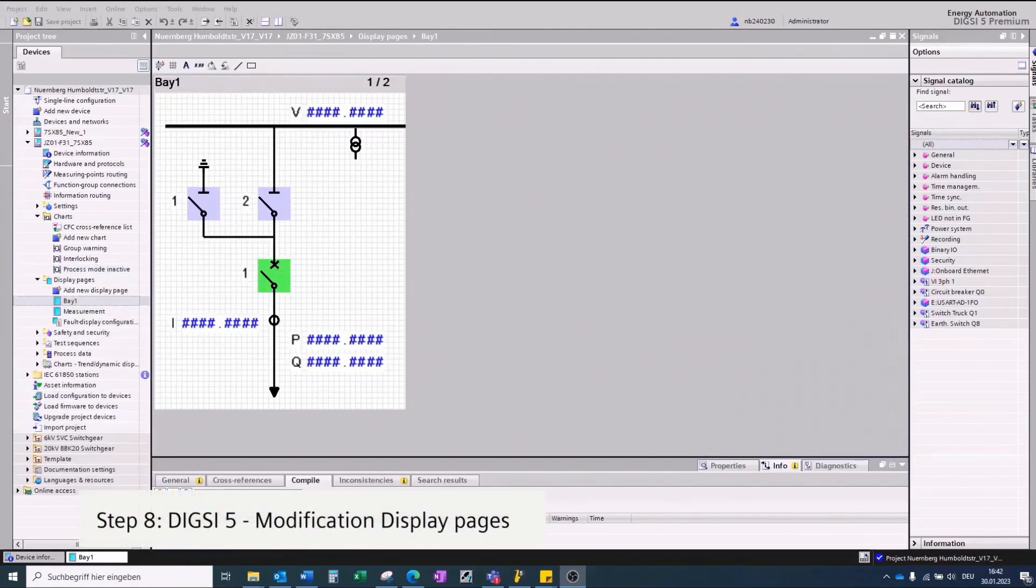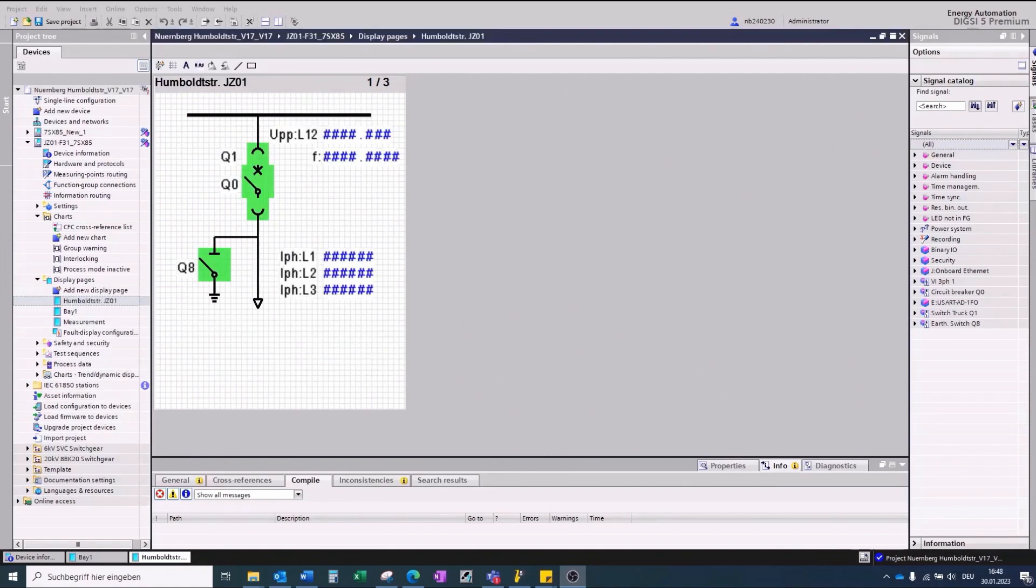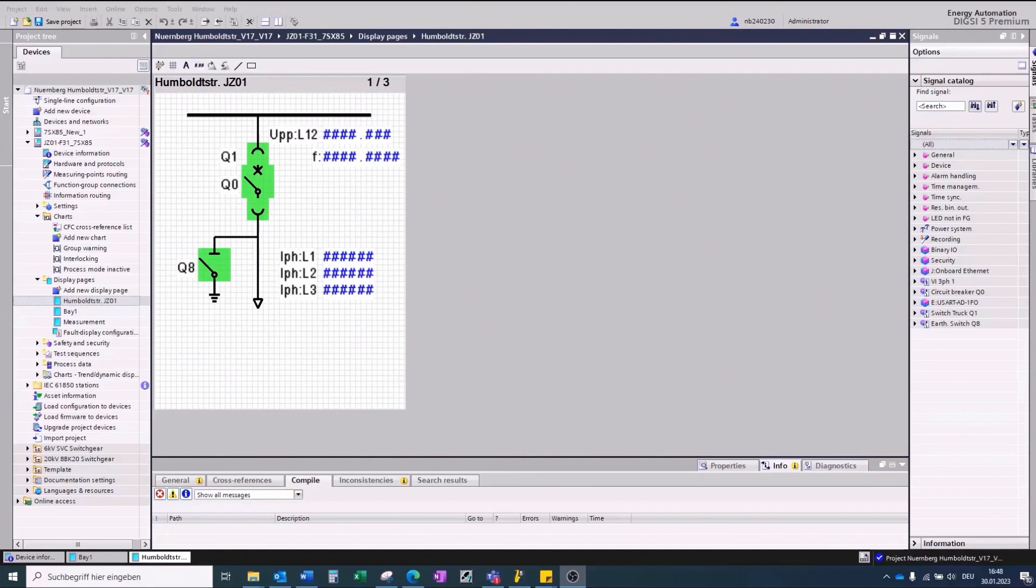Migration Step 8, modification of display pages. The pre-configured display page does not match the primary bay single line because in the 8BK20 switchgear bay the line earthing will not be realized with the circuit breaker on position but directly on the cable. So, we recommend using an adequate display page like the following example. The device display pages can be imported and exported with the .dsp5 file format.